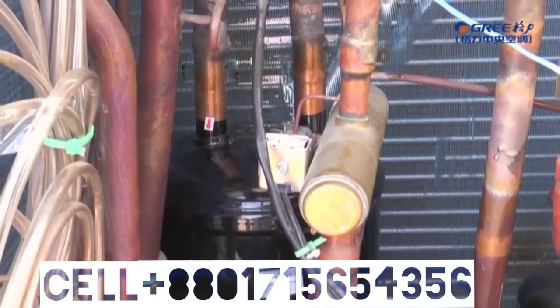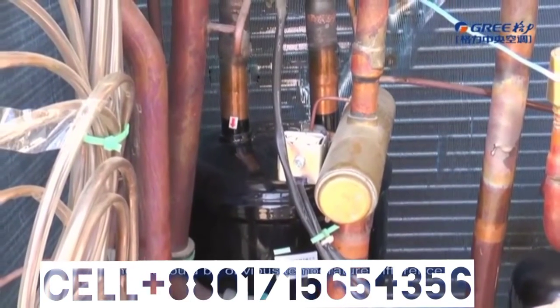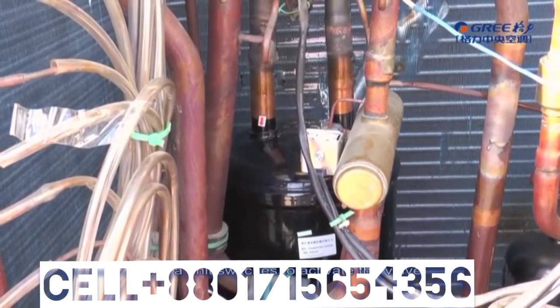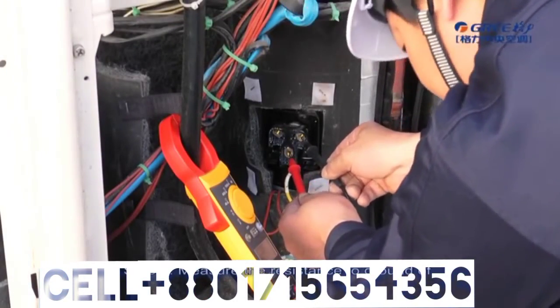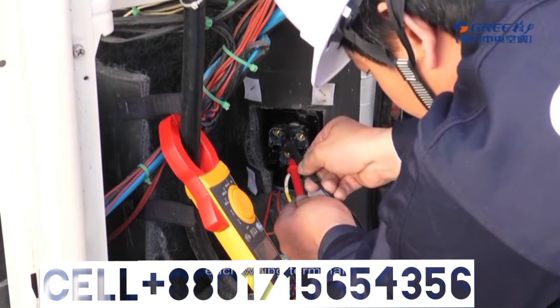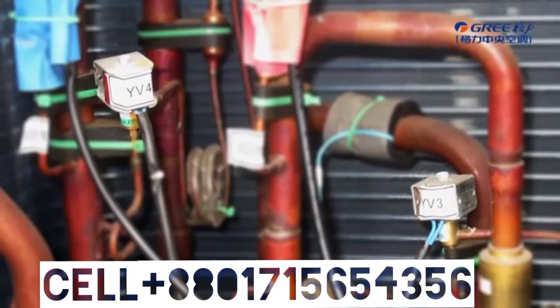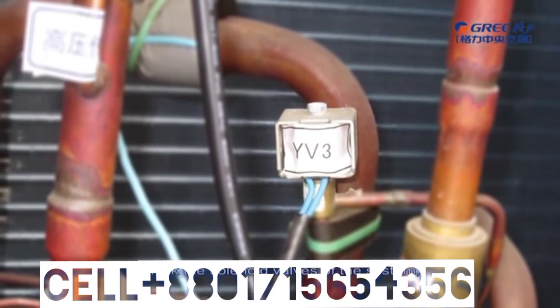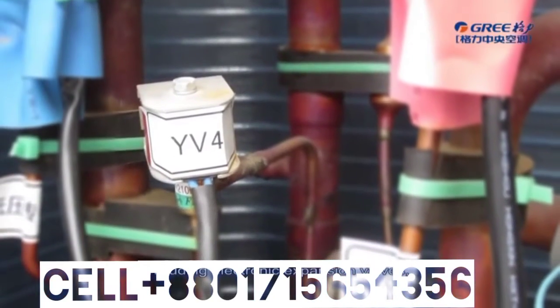Step 4. Check whether the four-way valve works properly. While this valve is normally running, there should be an obvious temperature difference between the 4 couple pipes connected. When the unit switches to activate the valve, there will be obvious vibration and sound. Step 5. Measure the resistance to ground of each wiring terminal. The value should be 10 megaohm. If not, the compressor is damaged. Precondition 2. The unit cannot be normally started. Check the solenoid valves of the system, including electronic expansion valves, oil return valves, and oil balance valves. Refer to the previous section for the test method.